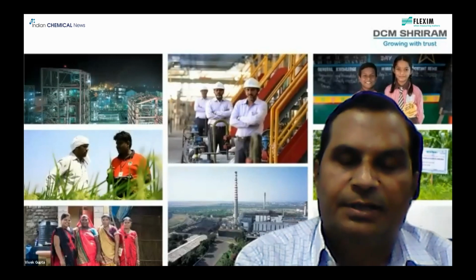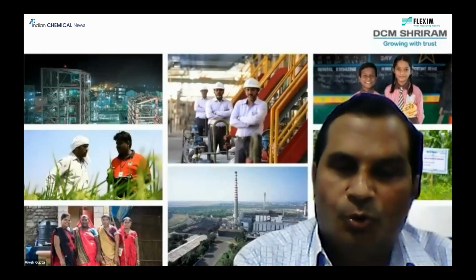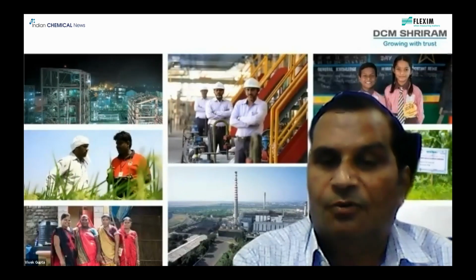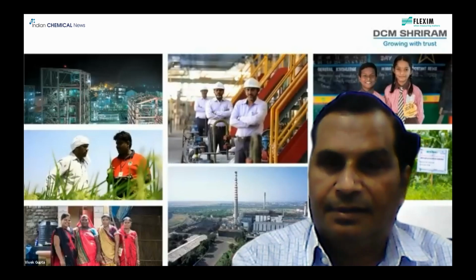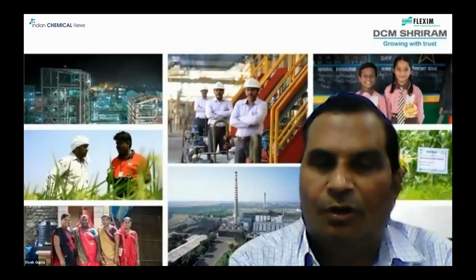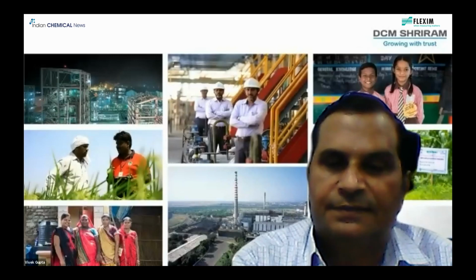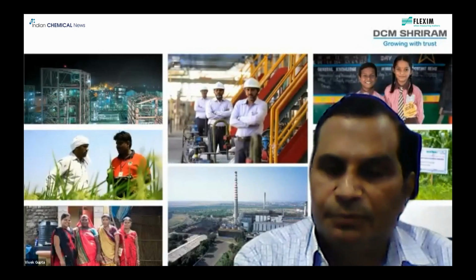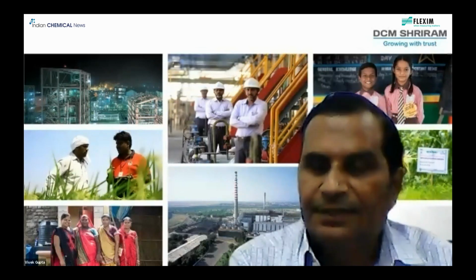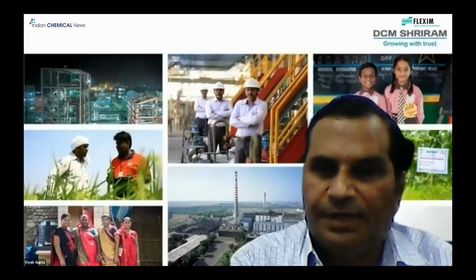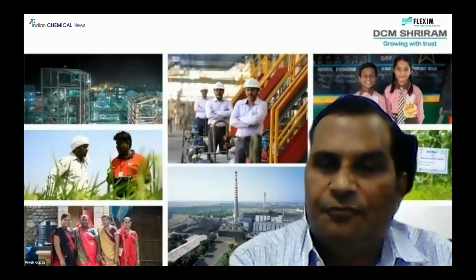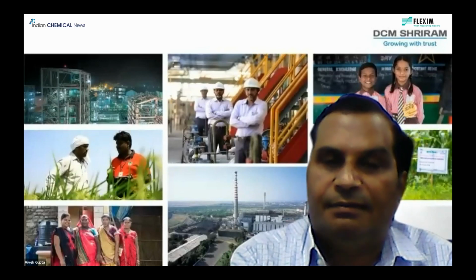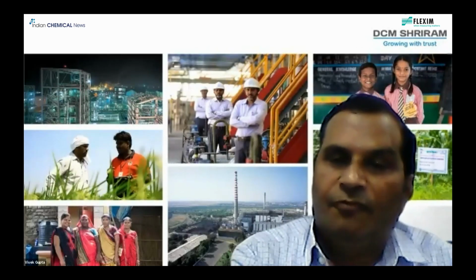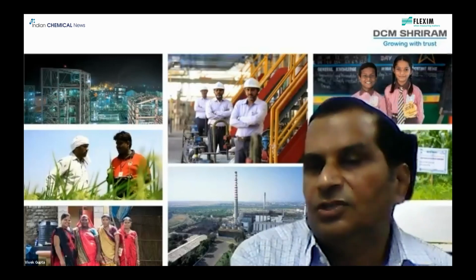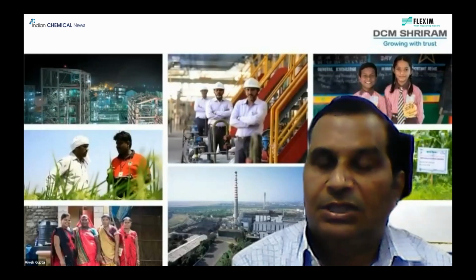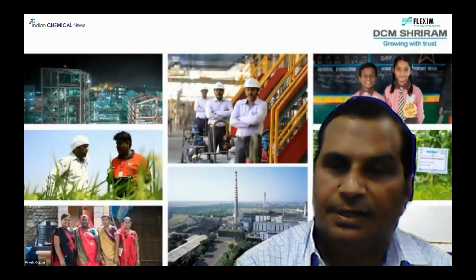Sometimes, for this lubricating oil cooling arrangement, people in the control room are able to see the reading, but the field operators are also very easily able to see it and find out if there is a relay contact. The relay contact will come when the flow has gone low. Earlier, we had installed a flow switch, and each of us is well aware that flow switches are prone to failures, sometimes because of impurities, sometimes because of mechanical contact. So we installed this clamp-on, and I cannot say a good experience so far, but I feel this will work well and give us a good reading of whether the oil flow is proper or not, and immediate attention to the control room operator to take the needful corrective action. So these are the things we have installed at Shriram so far.